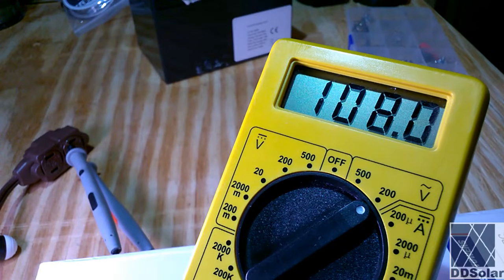This is where multimeters really start giving you information that you might not otherwise have or even be aware of. Let me turn the heater off and I will explain. And the heater has been turned off, and you can see the voltage returns to its normal range. In this case, the reason the voltage dropped to 107 volts, which is considered to be below spec, you would not want to be lower than about 110 volts in North America.